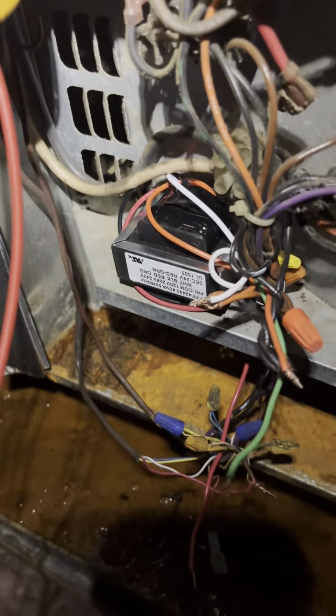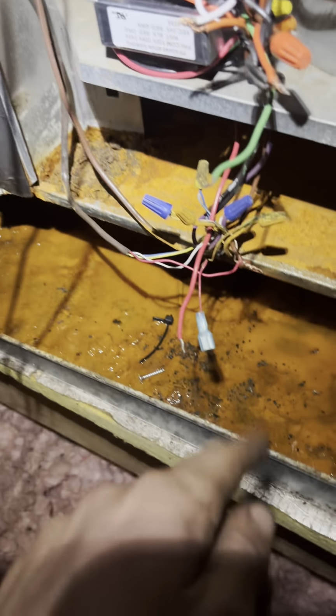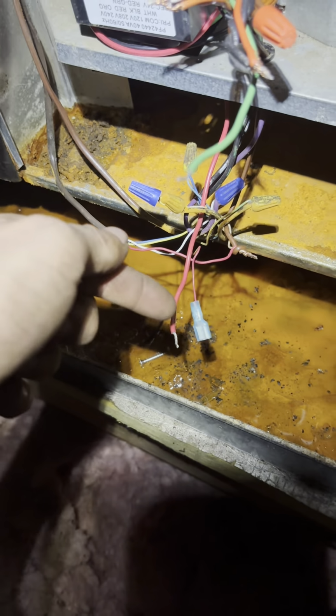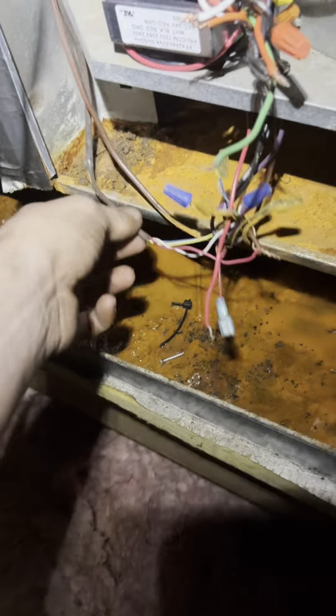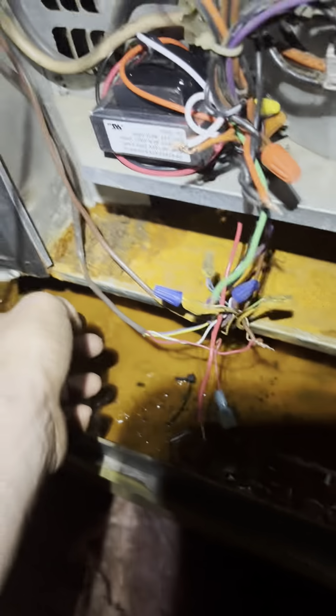Now we need to go down and see why this transformer blew, because transformers don't just blow. That usually means that that brown wire, that green, crossed with that red somewhere along the line through these thermostat wires. So let's go find out. All right, so like I was saying, something probably blew the transformer. I looked upstairs in the attic, but I couldn't see anything.